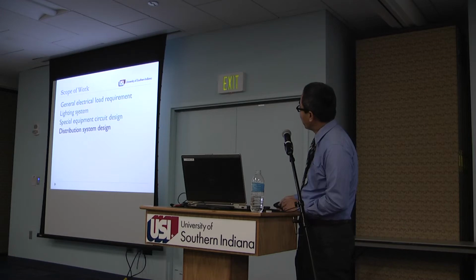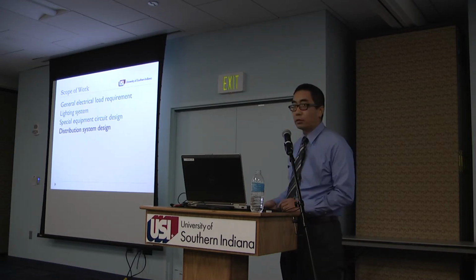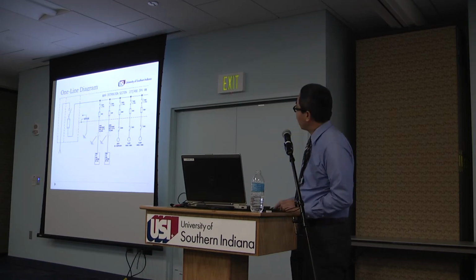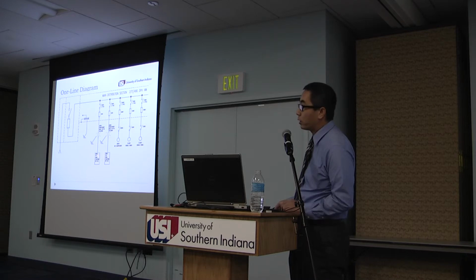So we're done with the general electrical, lighting system, and special equipment. And the last one will be a distribution system to tie them together. And here's the single line diagram. We have the power entrance here, and a transformer here to supply power to the lighting and the receptacle panel. And there's another transformer to supply the paint booth. And there's other special equipment like motor, compressor. Will have this dedicated circuit.